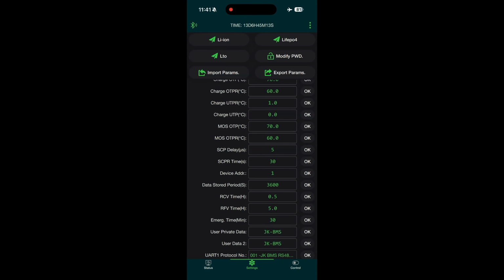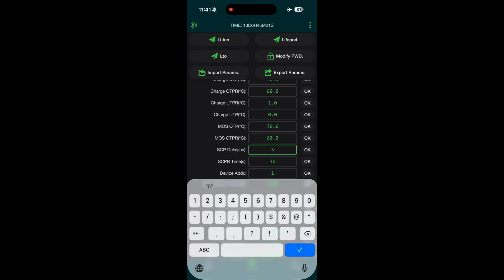Okay, the SCP stands for Short Current Protect Delay. Okay, this is basically if the BMS detects a surge in current, typically caused by a short circuit, how many seconds, or actually microseconds, do you want to wait until the BMS disconnects? Okay, so it's currently set to 5. If you wanted to change that down to 3 seconds, then you can do that.